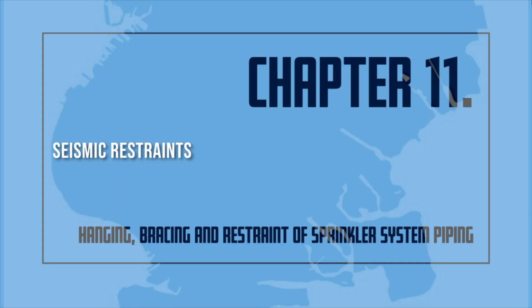Seismic restraints. The New York City Building Code adopted earthquake code requirements. This reclassification requires the installation of sway bracing for earthquake protection be installed on sprinkler systems in buildings built after 1998. The system piping shall be braced to resist both lateral and longitudinal horizontal seismic loads and to prevent vertical motion resulting from seismic events.